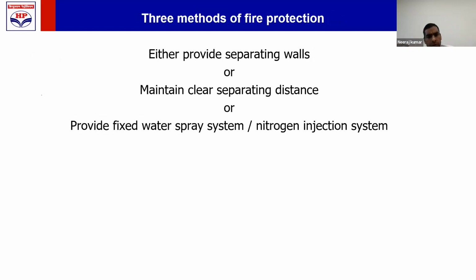Now, the entire principle of fire protection for transformer is based on providing either of the three things. What are those three things? Either you provide a separating wall, which will prevent the fire from spreading to the other installation, or you provide separating distance, clear separating distance, so that even though your transformer catches fire, there is no other equipment or installation near to it, and so other installation will not be affected. So you provide such clear separating distance if you are not able to provide separating wall.